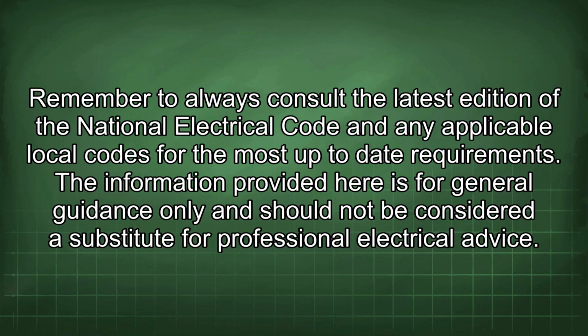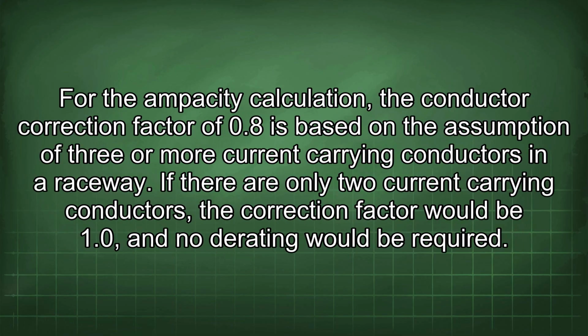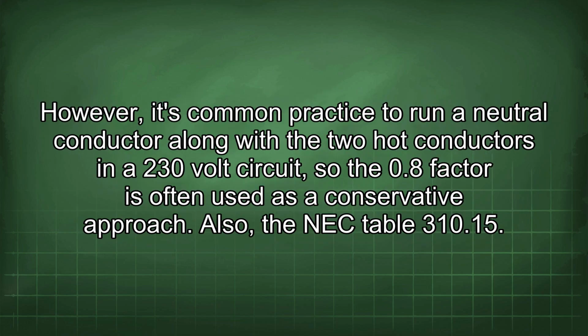for professional electrical advice. For the ampacity calculation, the conductor correction factor of 0.8 is based on the assumption of 3 or more current-carrying conductors in a raceway. If there are only 2 current-carrying conductors, the correction factor would be 1.0, and no derating would be required. However, it's common practice to run a neutral conductor along with the 2 hot conductors in a 230-volt circuit, so the 0.8 factor is often used as a conservative approach.